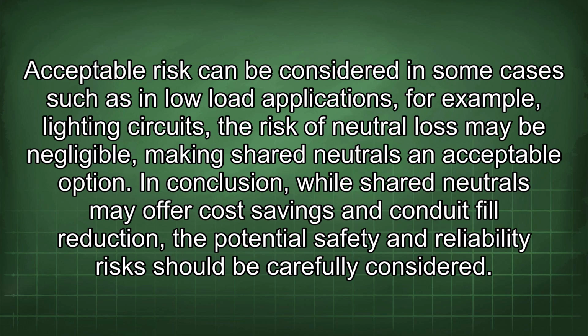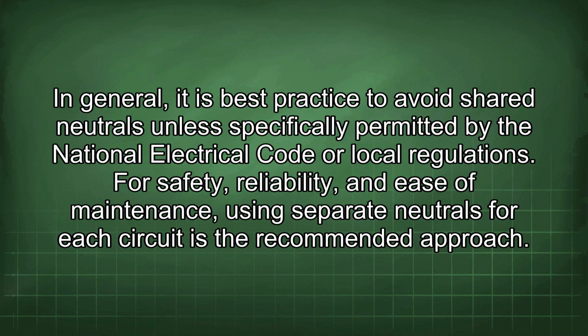In conclusion, while shared neutrals may offer cost savings and conduit fill reduction, the potential safety and reliability risks should be carefully considered. In general, it is best practice to avoid shared neutrals unless specifically permitted by the National Electrical Code or local regulations. For safety, reliability, and ease of maintenance, using separate neutrals for each circuit is the recommended approach.